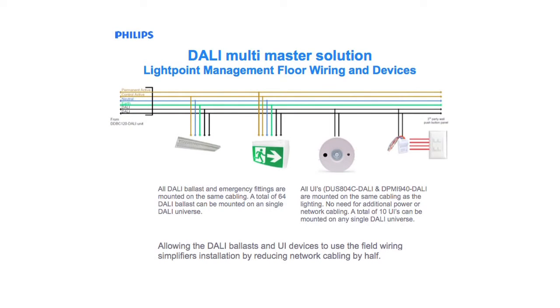The user interface devices, contact devices, are connected directly onto the DALI network, like all the other devices, and do not require any additional network cabling to function. The user interface devices do not consume any of the traditional DALI 64 addresses, as they have a different method of addressing. There can only be 10 user interface DALI addresses on a single network. By using DALI MultiMaster, a project can effectively cut the network cabling requirements by half.